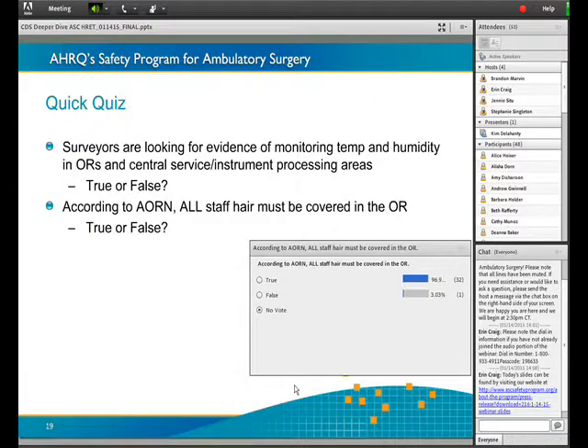But I want to go into a little more detail about the sterilizers. Not only are they looking for monitoring temperature and humidity in the ORs, they're also looking to make sure you're at the right pressure. A decon area, where you're doing decontamination of instruments for sterilization or high-level disinfection, must be negative pressure. To remember this, I always say dirty bugs stay in, so negative pressure is in, and that way it doesn't go out into the ambient air.